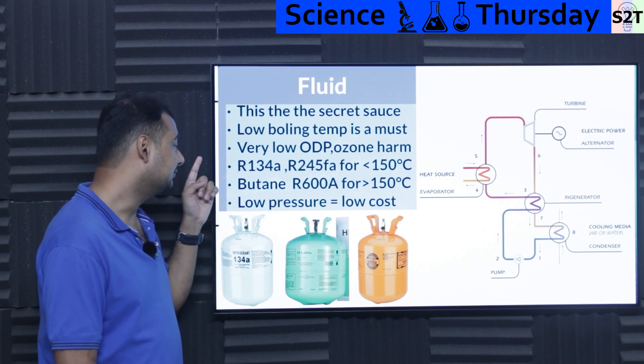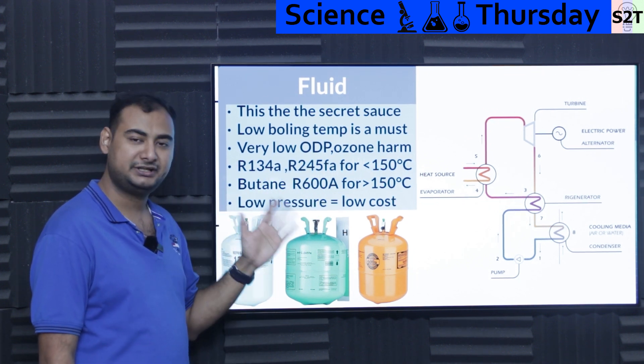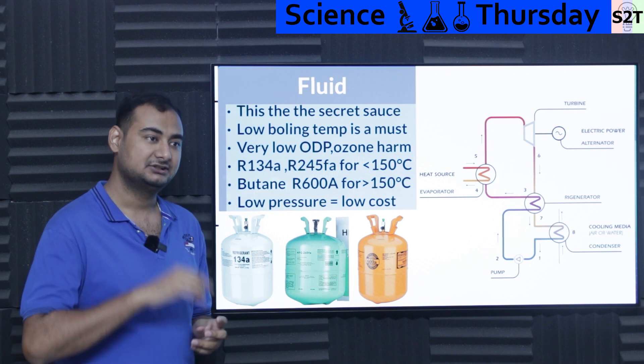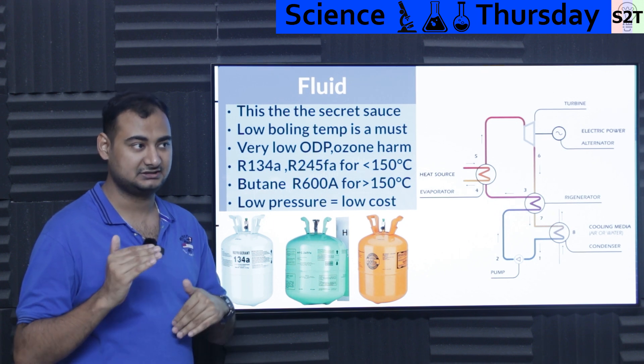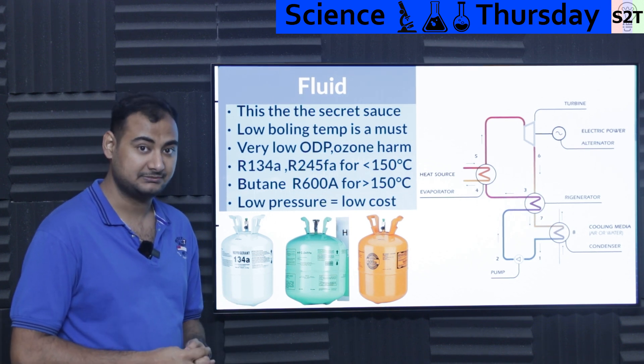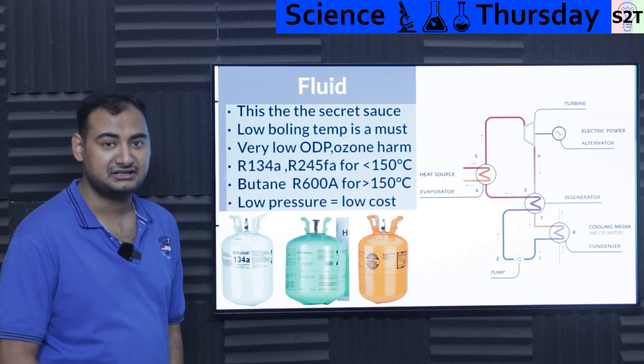There are broadly three fluid options. First, R134a and R245fa — these are HFC gases generally preferred when the hot side is below 150 degrees Celsius. They have different characteristics so it depends which suits your application better. When you're talking about higher temperatures or more serious workloads, butane — R600a — is used, and is generally preferred for heat sources above about 150 degrees Celsius. There's a Turkish geothermal plant of around 22 megawatts using butane.